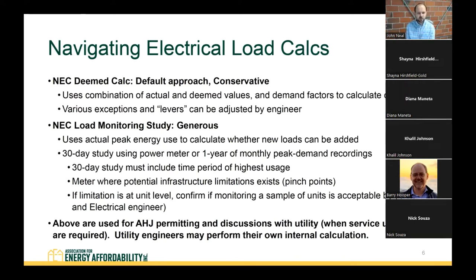It uses both proposed equipment and some deemed values when determining if there's enough capacity in the building. And while there are some exceptions and levers that can be pulled, it still typically produces a conservative result. We've had good success with engineers using what they call a load monitoring study that looks at the actual peak demand in the building, either during a 30-day representative period across the year, or peak demand values across an entire year.